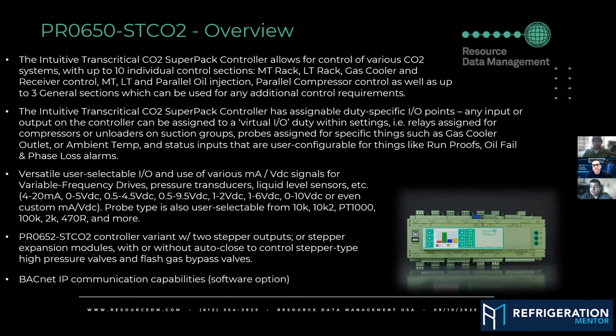Can you explain that? So at room temperature, very little. I think it's something like 200 ohm difference. The difference comes into play when you get fairly cold. Your resistances are quite a bit off, to the point where you can be reading 4, 5, 6 degrees off at a colder temperature if you have your probe set wrong, or if you're using the wrong type. So it does matter for below room temp applications for sure. At room temp, you're almost not going to be able to tell the difference between the two. Yeah. And this is the big thing I talk about with a lot of people, because I didn't know about this, like, oh, a 10K sensor is a 10K sensor. But no, even if they're 10K sensors, they'll have different resistance charts. Some are fast acting, some are slower acting, even though they're a 10K, just like you said. So that's a very good point that you put out there. Thank you for pointing that out. I think there's also a 10K3, so have fun with that one. It's a 10,300 ohm at room temp, so it's slightly different.